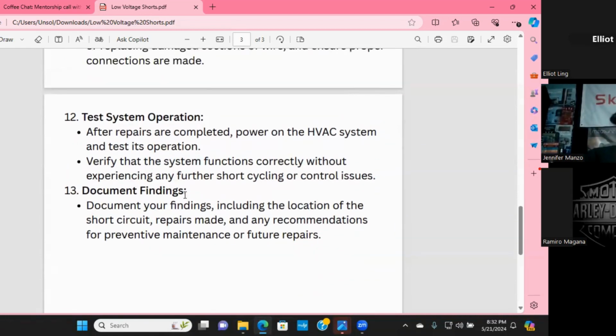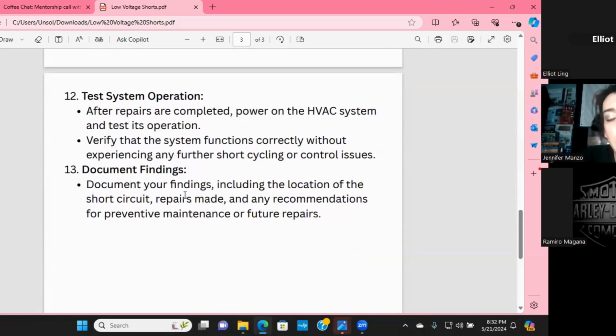And then after that, this is the important part, you guys. So many guys call my tech support line and they say, the unit was acting weird. I replaced the board. First of all, there was no other troubleshooting in between those two sentences. It was acting weird, so I replaced the board. Already a no-no. But on top of that, they don't wait to see if it operates correctly with the new board installed. And so 5 minutes down the road, an hour down the road, whenever it gets warm in the house again, they're getting a call back that says, still doing the same thing. You fixed nothing. And then you're going back there and you're now at 5 o'clock at night because you didn't want to wait, and you're troubleshooting a low voltage short all night long after you already billed the customer for a board. Never a fun thing. Callbacks are not something we want.